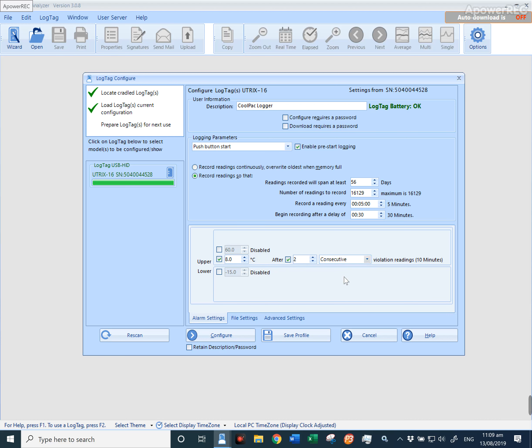If you want to be notified for an upper alarm limit when it goes out at 8 degrees, the logger will flash red. You can also add a cumulative or consecutive alarm.